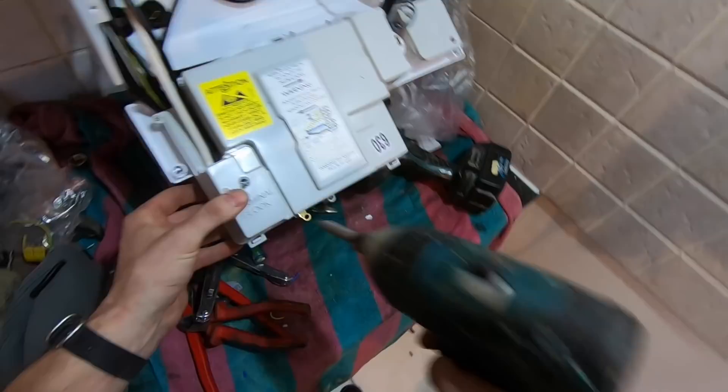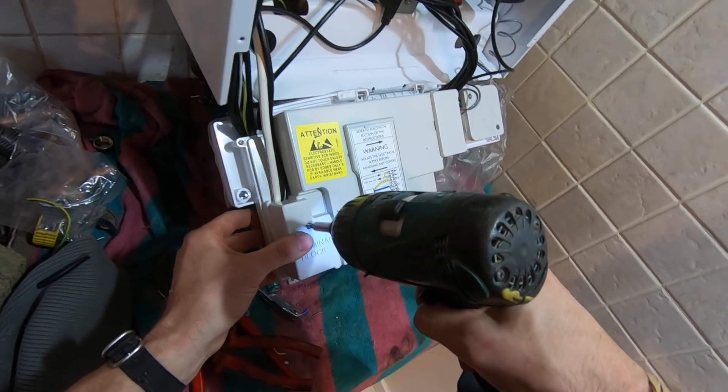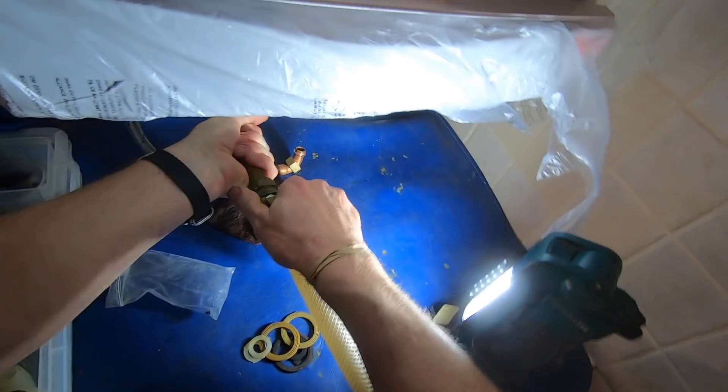Nice and tidy. Time to power flush. Boilers are isolated, so push fit onto there. So that's one — go 22mm. So now we've got 22mm, 22mm, got hoses, fitting washer. Got the washer. Now remember — isolate the boiler so that you don't put any muck into the boiler. It's all tight there.